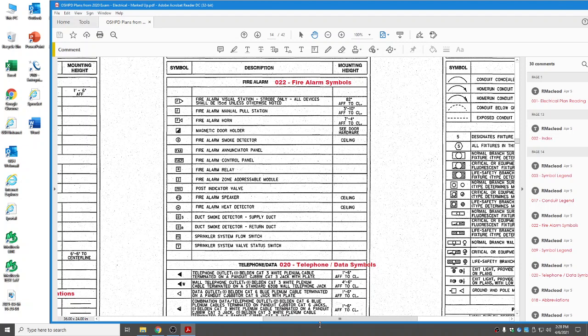And then we've got an FS, fire sprinkler system flow switch, which typically is at your riser locations on a floor-by-floor basis. If there's any flow in the system, it tells the fire alarm that you've got water flowing, possibly because a head popped and there's a fire somewhere. And also a fire sprinkler system valve status switch, which just tells you whether it's open or closed. All right, now we're going to go ahead and take a look at a floor plan and take a look at where these symbols are placed.